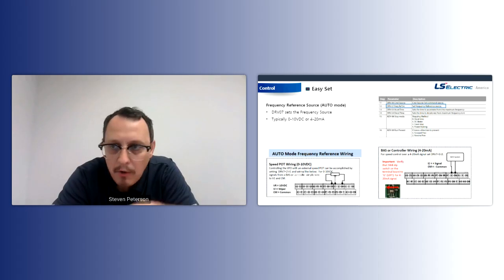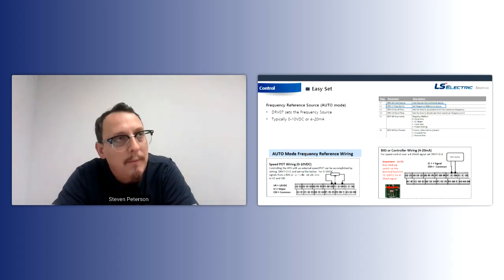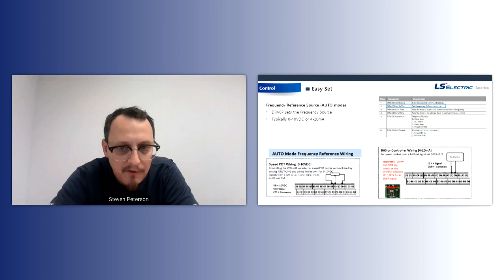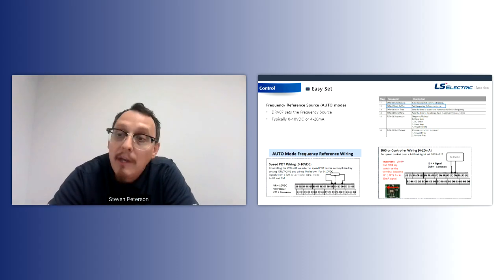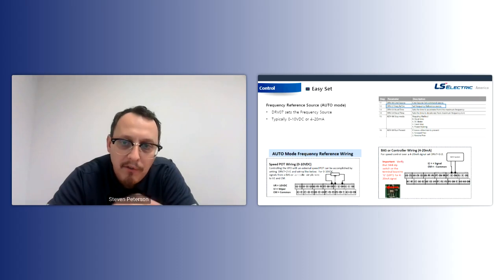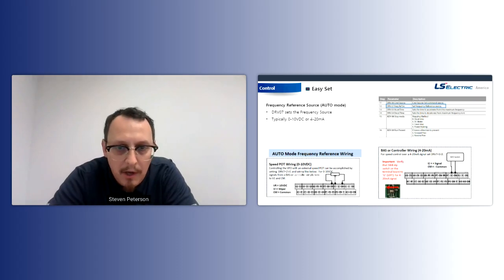0 to 10 could be 2-wire or 3-wire. If it's 3-wire, it's typically because you have a speed pot, and the speed pot's a voltage divider. So that's the picture on the left here. It could be 2 wires. In that regard, you'd go to V1 and CM, with CM being your common. You'd go to this parameter and you say, hey, look at V1. Okay, so V1 is 0 to 10 for us.